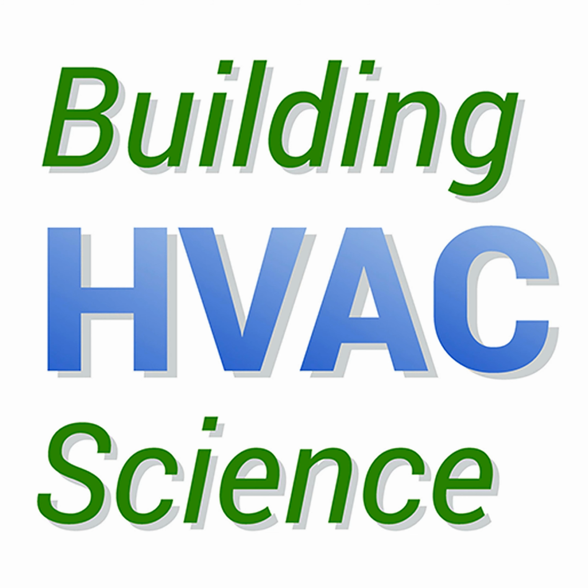On the higher end, back to those hospitals and schools, we're really talking about a DOAS with a hot gas reheat. I can almost make an analogy there as well. We're actually very similar to a hot gas reheat, where, again, you'd be coming off that coil at some dew point that you want to get down to. You want to reheat the air. So you're taking some of that heat that you pumped out and putting it back into the airstream to heat it up again. That architecture is basically the same refrigeration system for us.